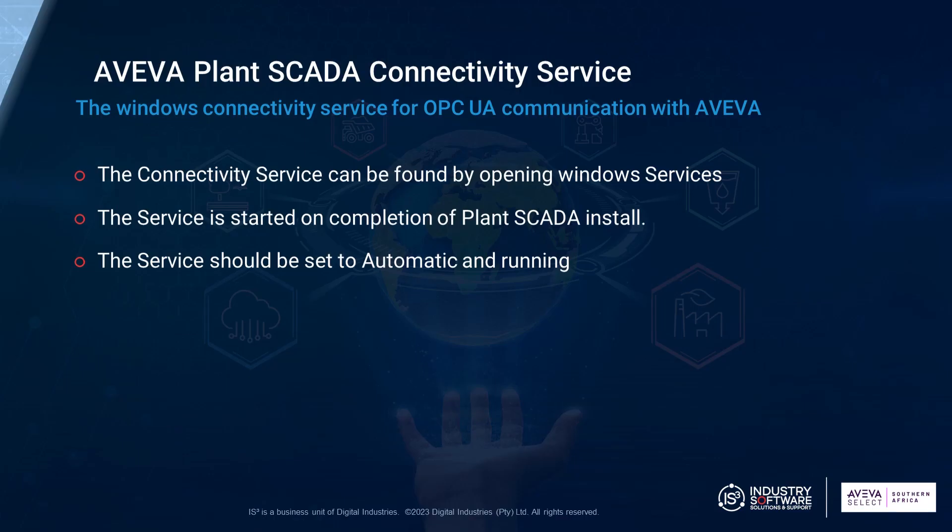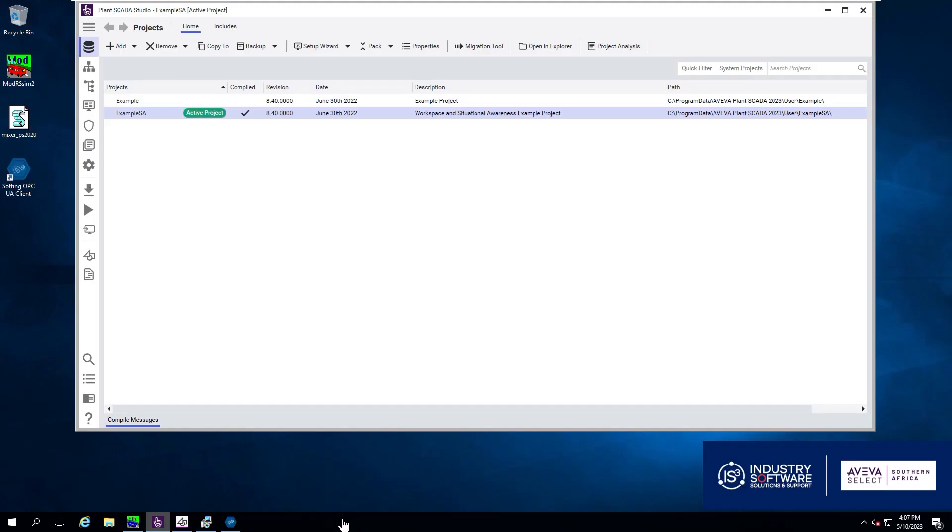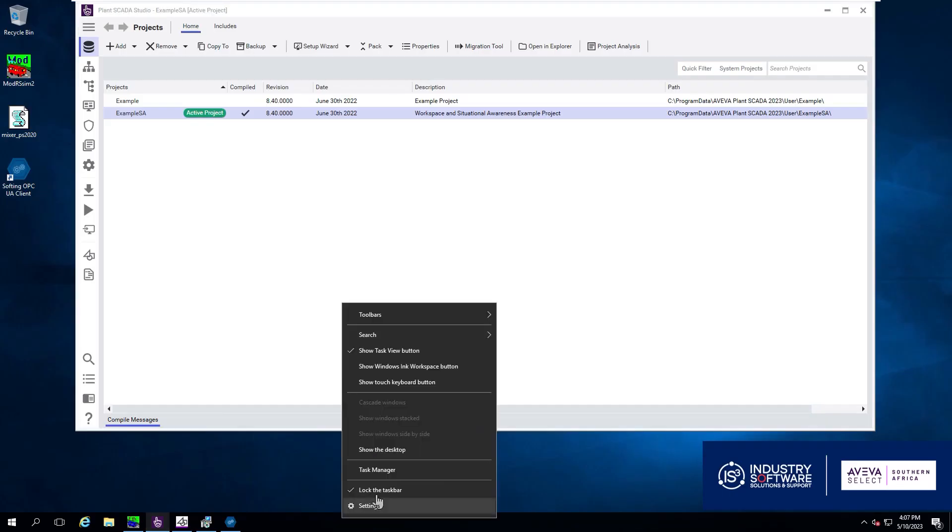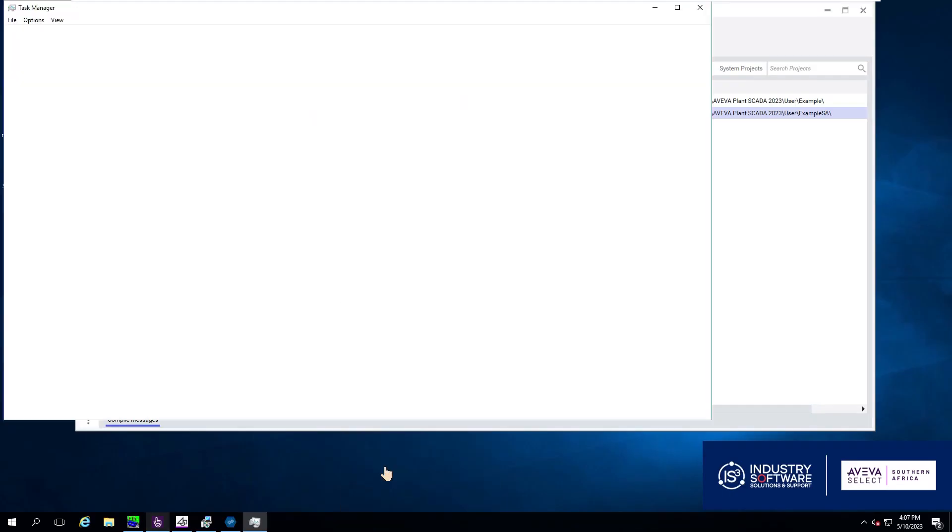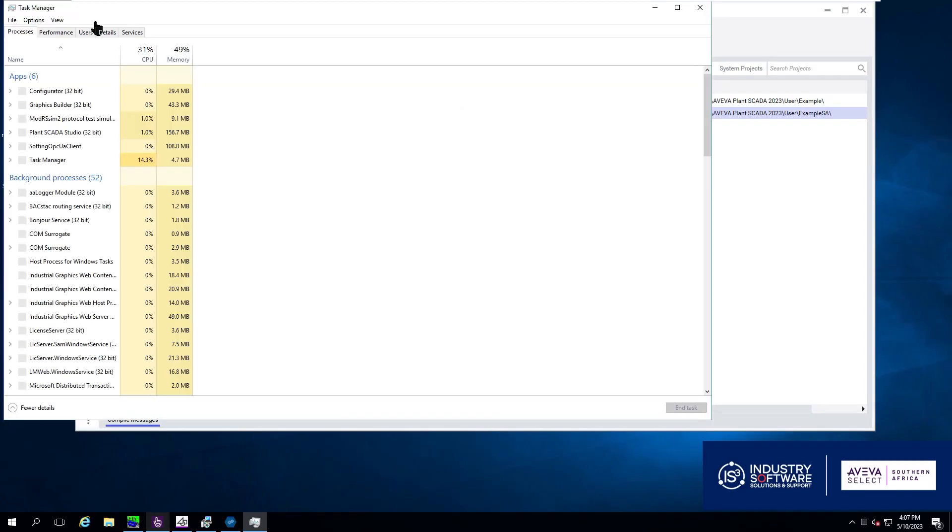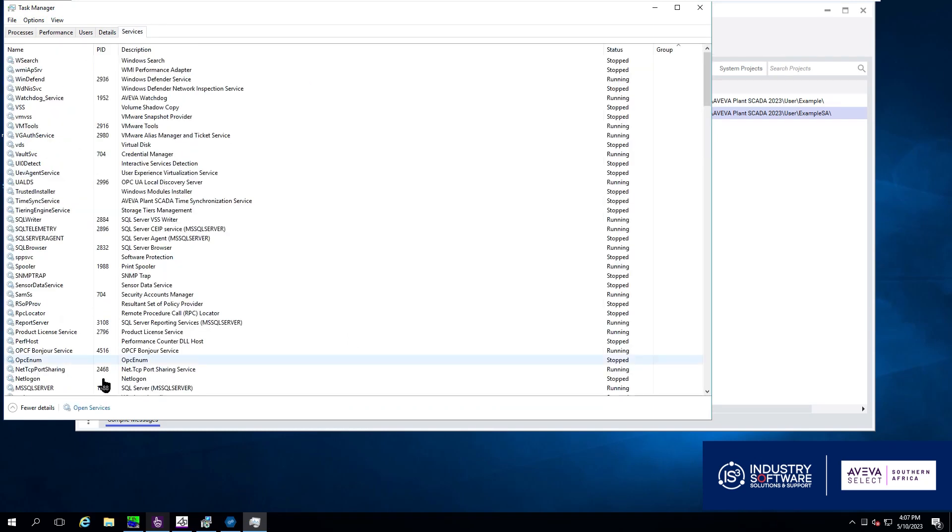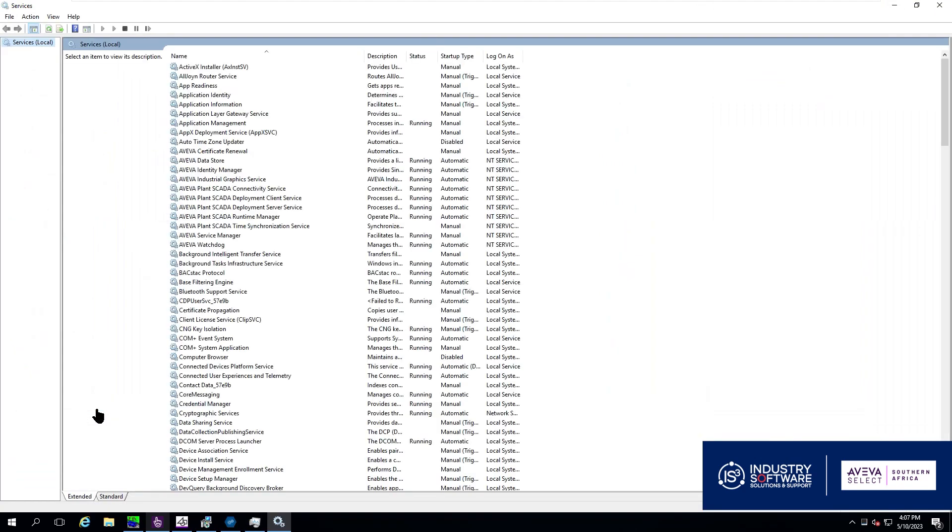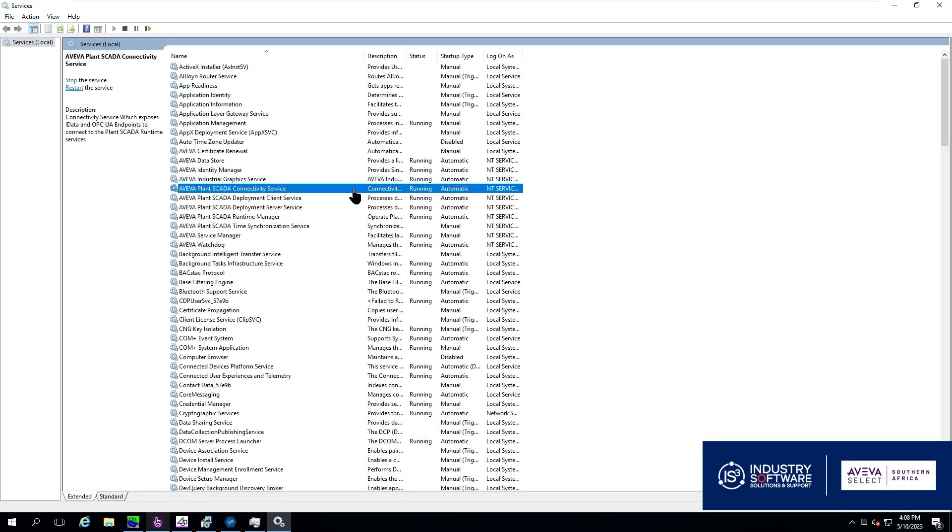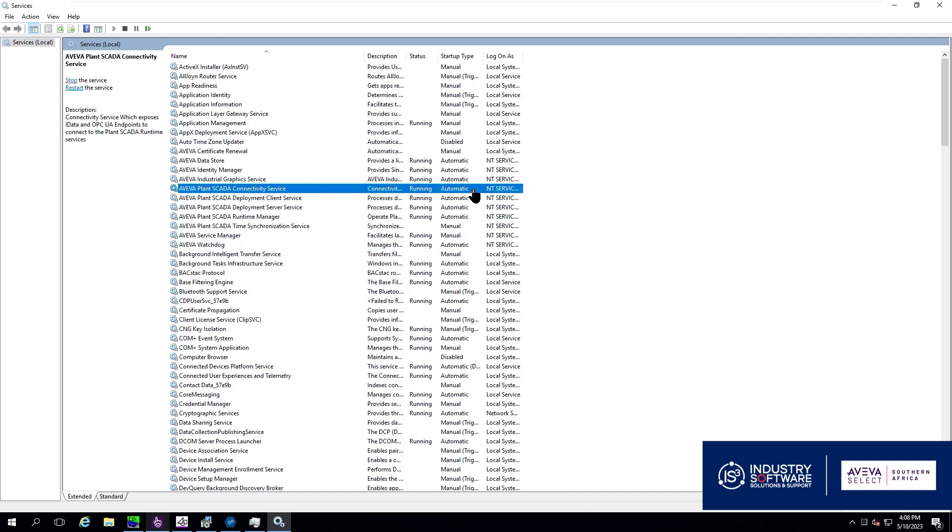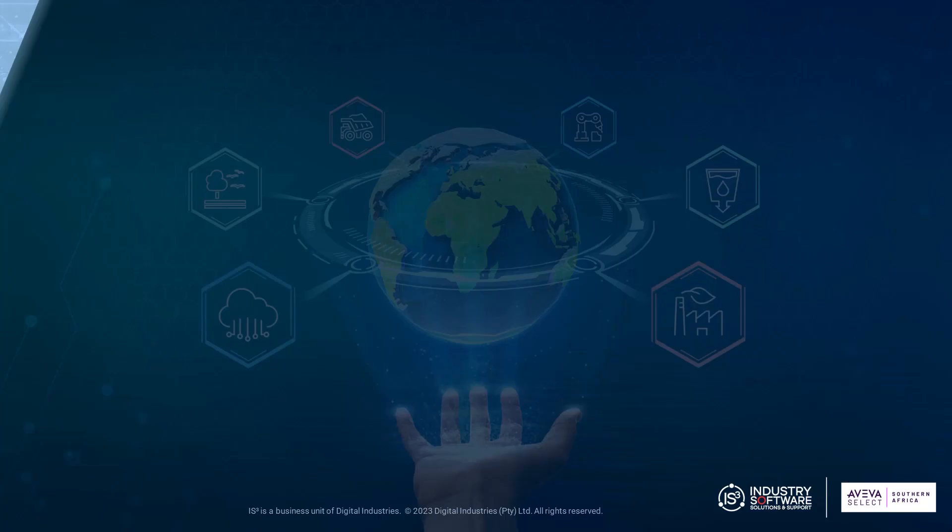Next up and lastly is the connectivity service. This is automatically set up when you do install PlantScada on your Windows machine and it will restart when your PC restarts if you have set it up correctly. So we are going to either go through task manager or control panel, we are going to open up our services and we can see our view of PlantScada connectivity services there. It is running and set automatic which is how we would like it so every time you restart a machine it works and that is how you set up OPC UA.